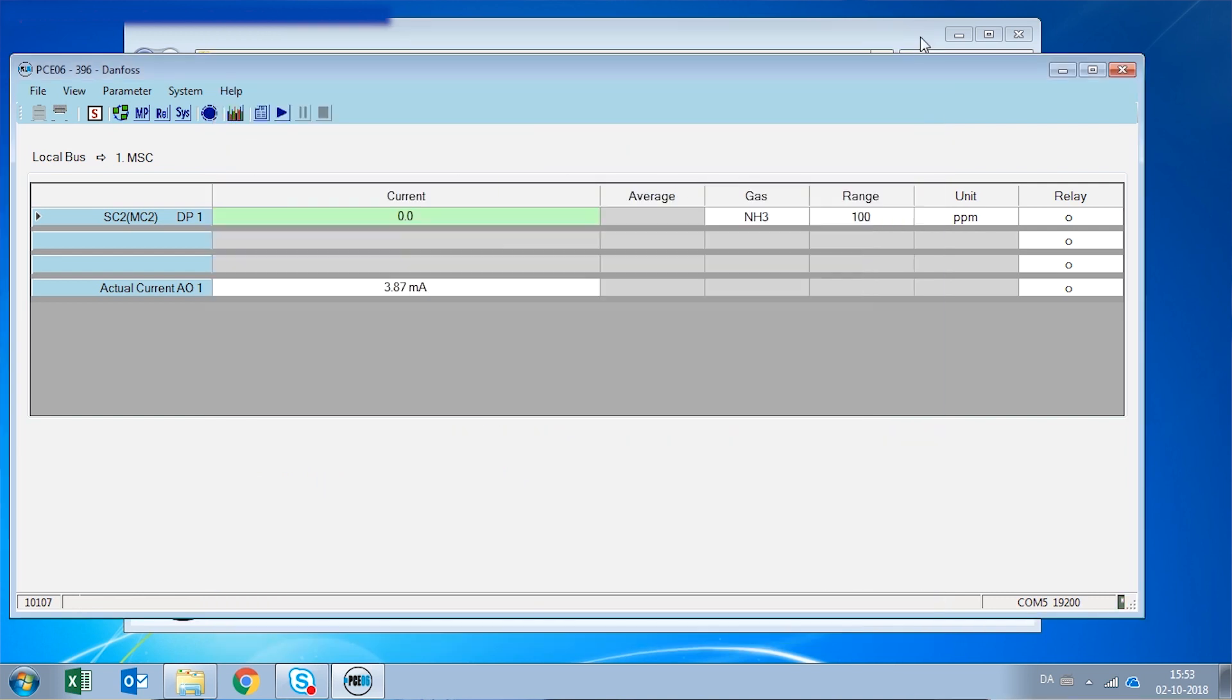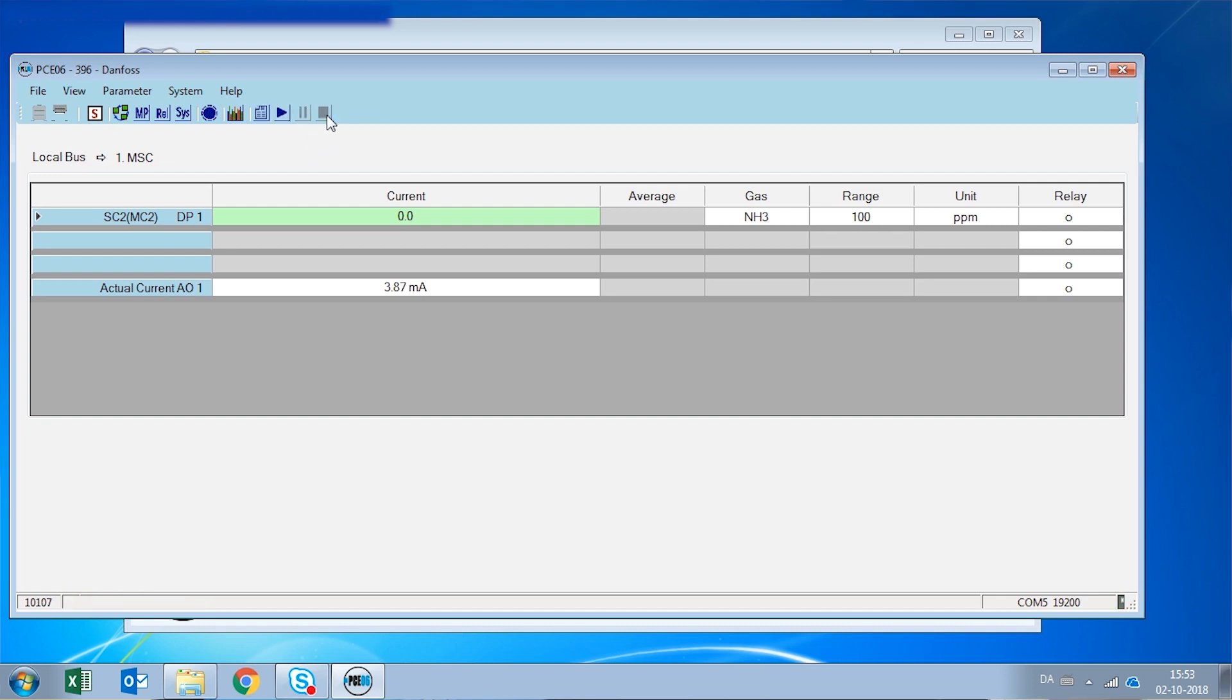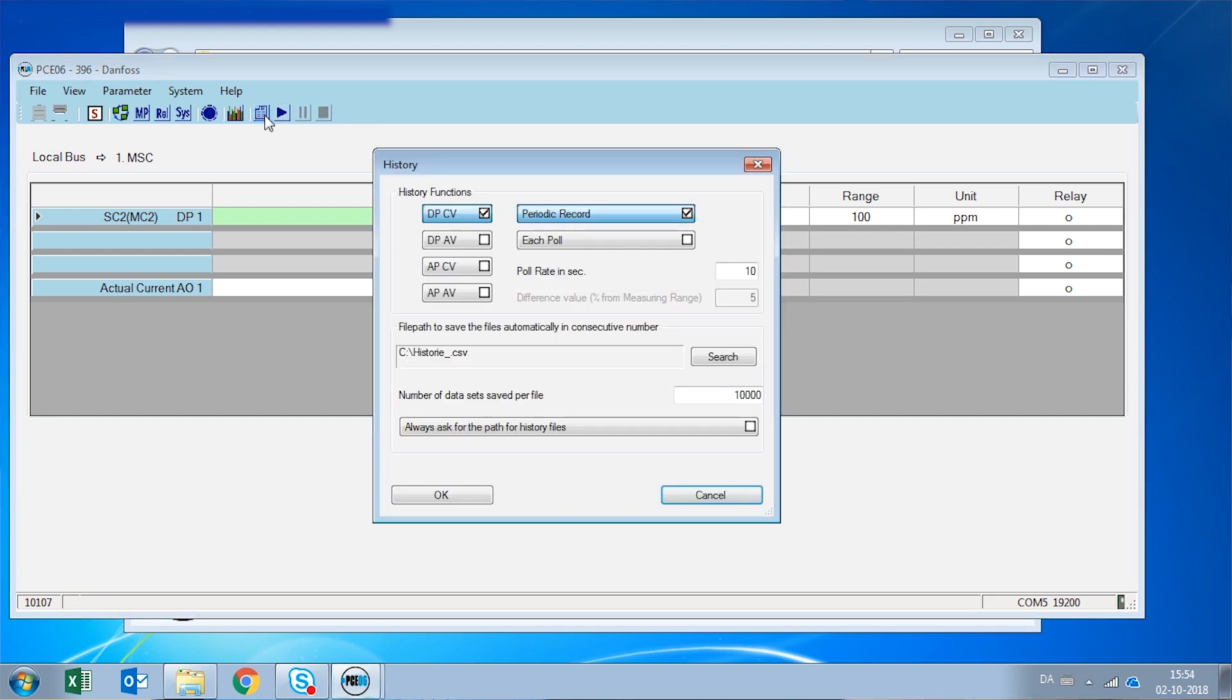And the final feature of the PC tool is that we can record the readings of this gas detector. So on this button here, if we click Start History, now it is recording all readings in ppm, alarms, errors, and any issue that the gas detector might present. And when we stop this recording, it's going to create a CSV file where we can see all these values.